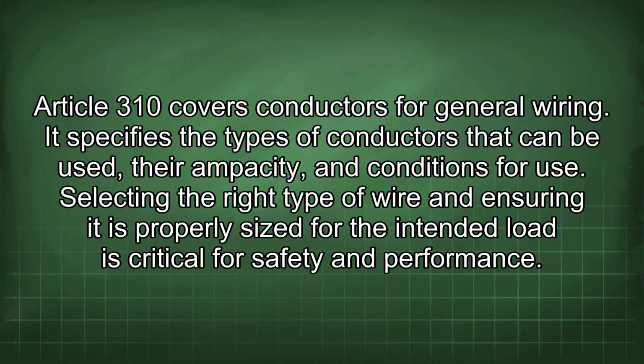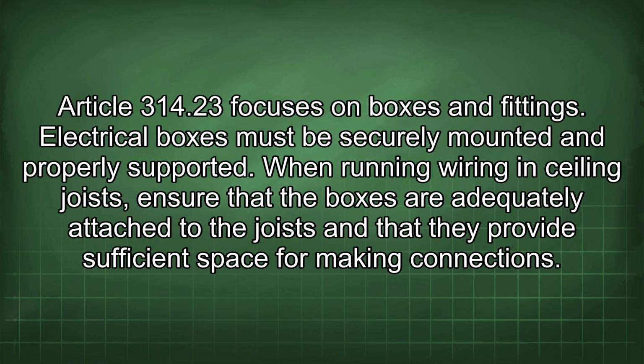Article 310 covers conductors for general wiring. It specifies the types of conductors that can be used, their ampacity, and conditions for use. Selecting the right type of wire and ensuring it is properly sized for the intended load is critical for safety and performance. Article 314.23 focuses on boxes and fittings. Electrical boxes must be securely mounted and properly supported. When running wiring in ceiling joists, ensure that the boxes are adequately attached to the joists and that they provide sufficient space for making connections.